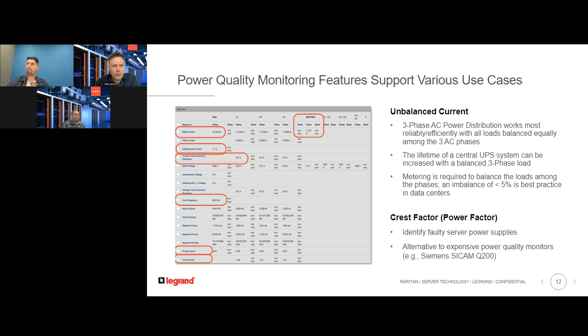Then another often used power quality measurement parameter is the crest factor, which is simply said the peak to average ratio of the AC current that flows in a conductor. In an ideal scenario, with an ideal sine wave AC current flow, the crest factor is 1.41, or mathematically expressed correctly, the root of 2. And any variation, smaller or bigger, identifies a harmonic distortion of the AC current sine wave.